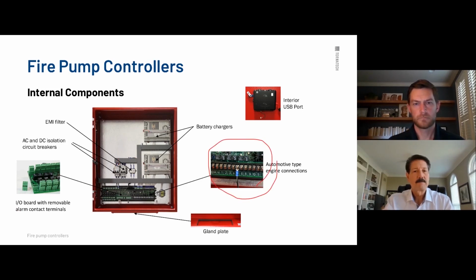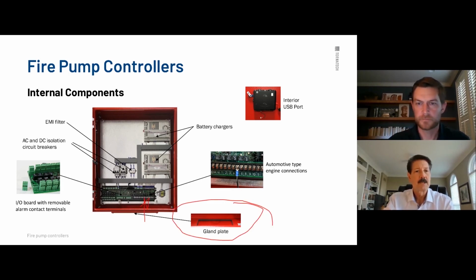1 through 12 is right here. That's industry standard. Doesn't matter what manufacturer engine you're using, 1 through 12 is standard. You know, 1 is the fuel solenoid, 2, 3, 4. These are all alarms. Normally it's a number 14 AWG. It's alarm wiring. 6, 8, and 11 are power. 6 and 8 are battery. 11 is ground. Those are power. And so there'll be labels in the controller that will tell you, I want a heavier gauge or dual solid cabling running to 6, 8, and 11, because that is, again, ground and battery connections. It's not just an alarm. It's carrying a lot more current. You still have your bottom gland plate. Makes it quite easy. Straight in wiring here. Pull apart terminals.